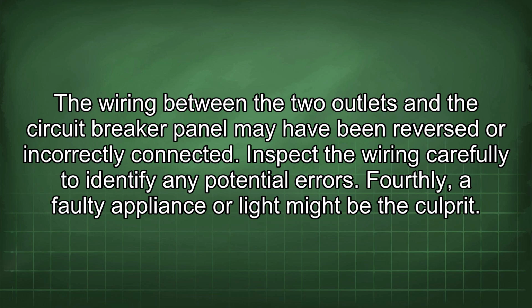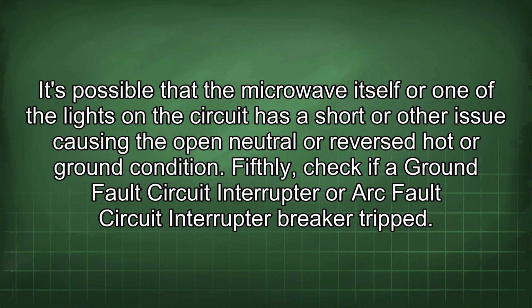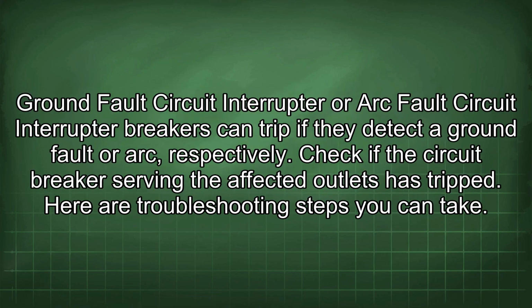Fourthly, a faulty appliance or light might be the culprit. It's possible that the microwave itself or one of the lights on the circuit has a short or other issue causing the open neutral or reversed hot or ground condition. Fifthly, check if a ground fault circuit interrupter or arc fault circuit interrupter breaker is tripped. Ground fault circuit interrupter or arc fault circuit interrupter breakers can trip if they detect a ground fault or arc, respectively. Check if the circuit breaker serving the affected outlets has tripped.